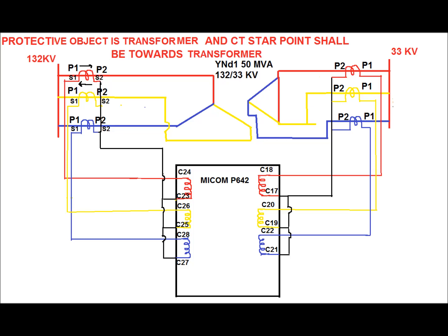Here the power transformer rating is 50 MVA, 132 by 33 kV. The HV side is Y connected or star connected and the LV side is delta connected, and the LV side phase shift from the HV side is 30 degrees lag.